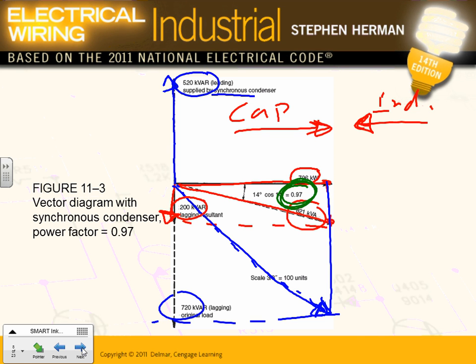Any comments, any questions about power factor correction? So, the larger the motor load, the more distance you want to keep from 100%, just because you'll have more fluctuation? You do, yes. When you have motors, you want to correct to between 93 and 97. If you have almost no motors, it's 98. If you have no motors, then there's no need for correction anyway; your power factor will be in the 90s. The only time you correct is if your power factor dips below 90. If your power factor by itself is 90 plus, no need to correct it.